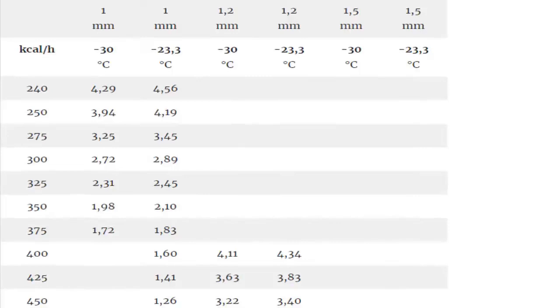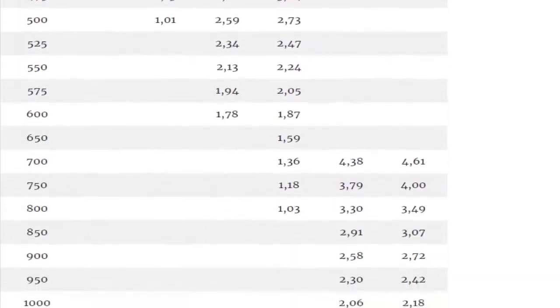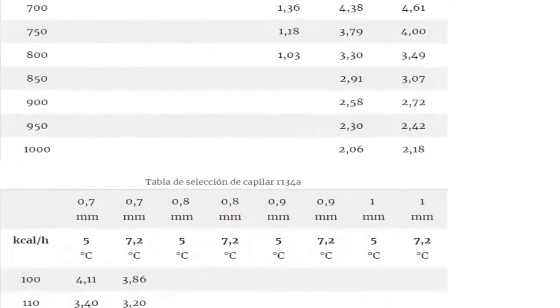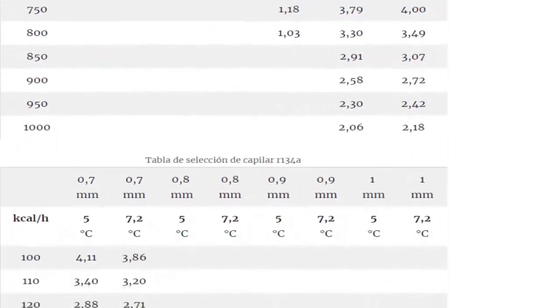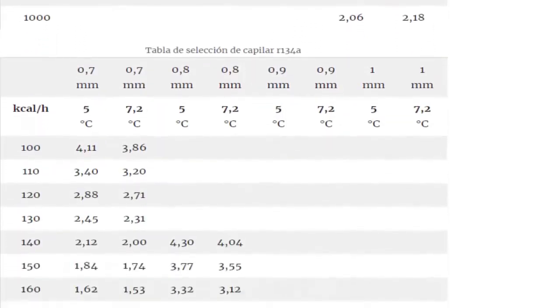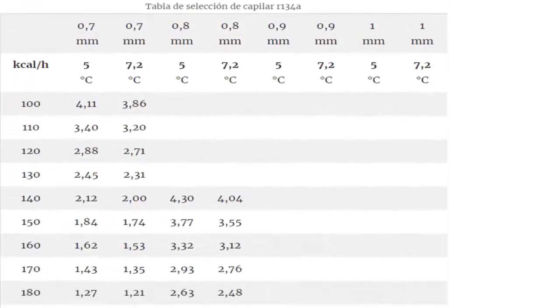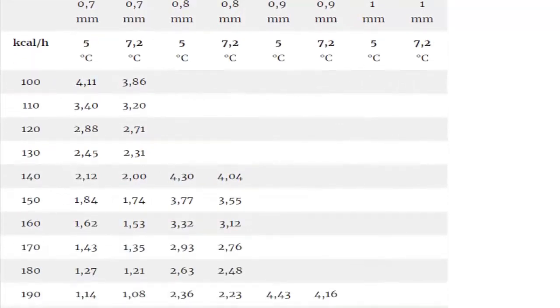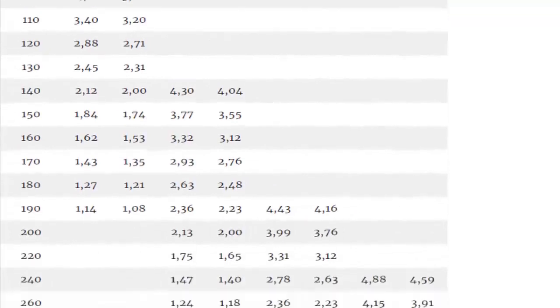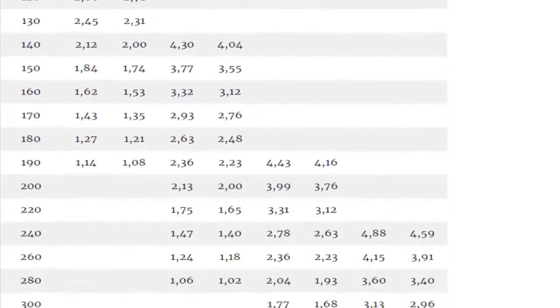5. There are tables that allow you to select the capillary taking as a reference the electrical power of the compressor motor in HP. However, it is best to use the cooling capacity of the compressor, measured in BTUs per hour, kilocalories per hour, or watts. 6. The problem with using HP as a selection parameter is that for the same HP value you can have different cooling capacities, since it will be influenced by the efficiency of the compressor.